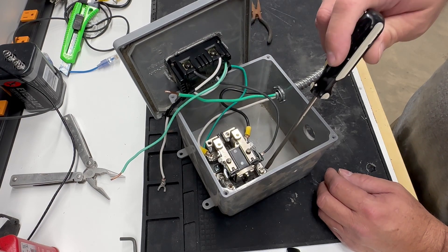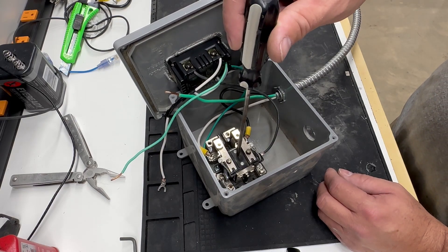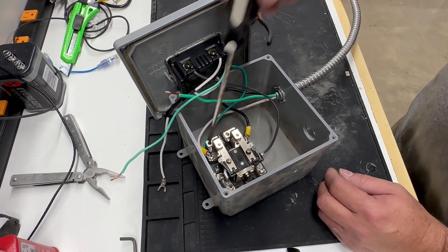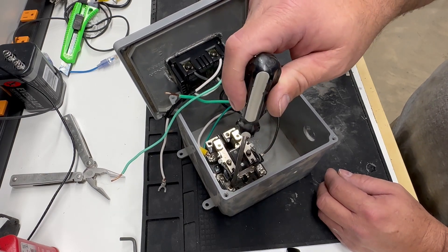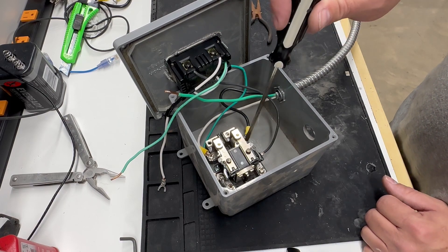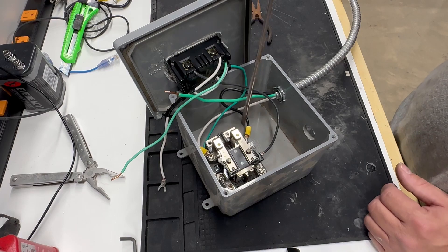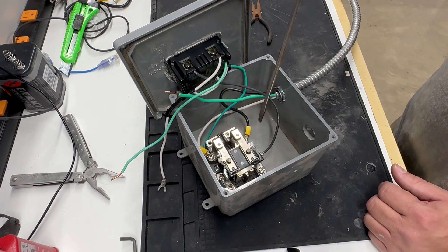So right now these connectors that are here and these connectors that are here are connected. When it energizes and pulls down, these connectors that are here will connect to these connectors that are here. So that's how you can pass your 220 volts from here to here or here to here depending on which way you want to be wired.